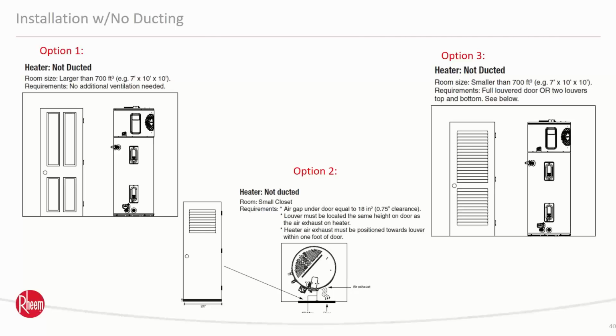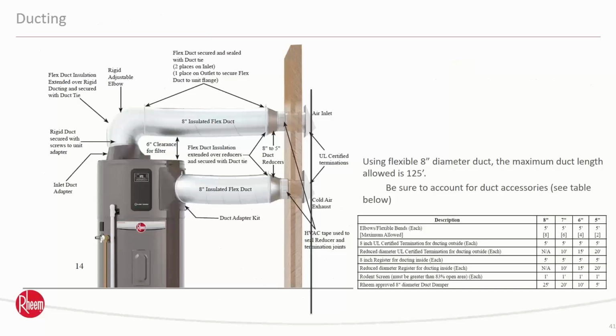That louver on top is going to be mounted so that the exhaust coming out of the top of it is going to blow through that louver so that you're not just sitting there recycling the air inside. And then if you look at the one on the far right, you can go to a full louvered door. It's going to do the same thing. Now, your other options we talked about were ducting. This is a picture of one ducted with, you can use 8-inch flex, okay? As far as duct lengths, if you look at this little table down here on the side, it tells you the lengths you can run up to.